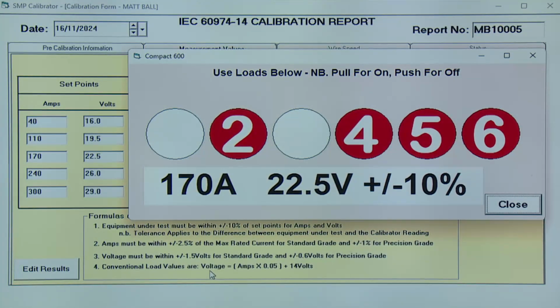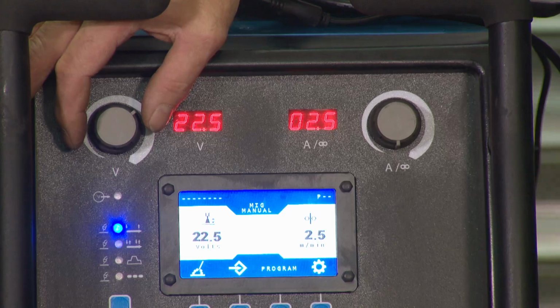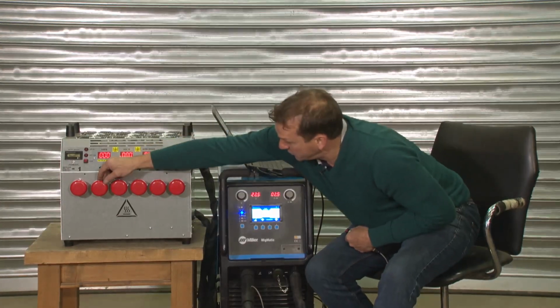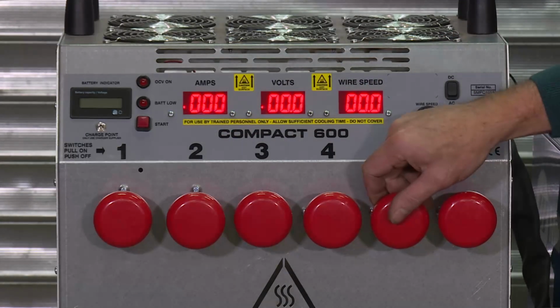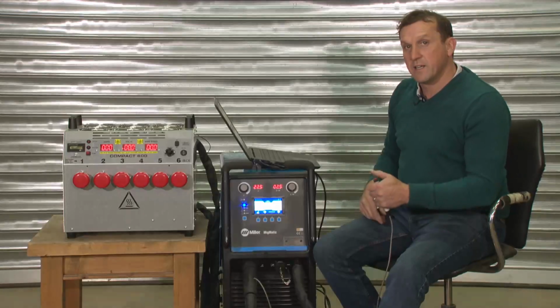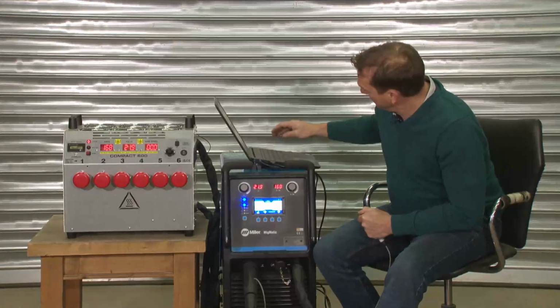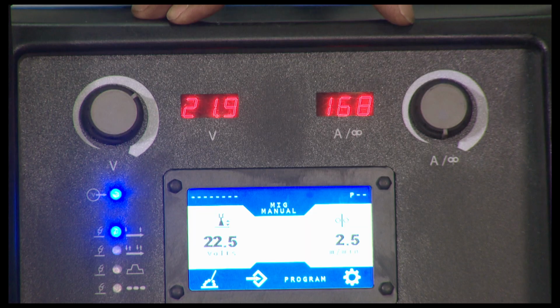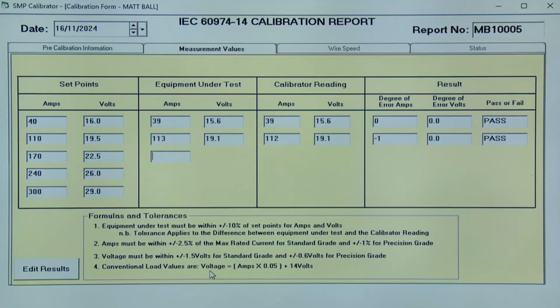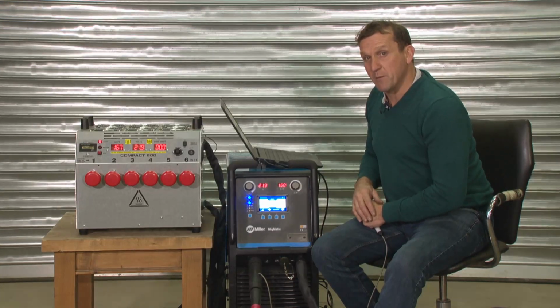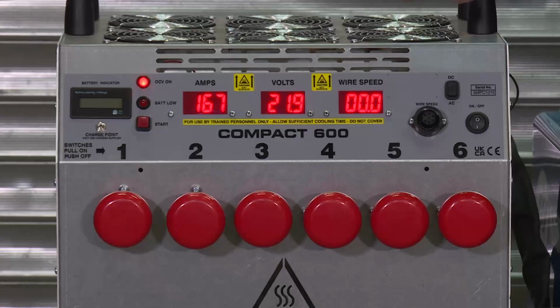Then we take our next reading, so we need 170 amps at 22.5, so we select 22.5 volts and load switches 2, 4, 5 and 6 and energize. We record the welder amps, we got 168 and 21.9. And then the calibrator reading, 167 amps, 21.9 volts.